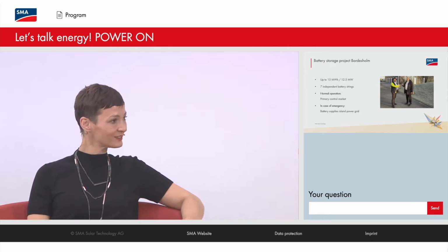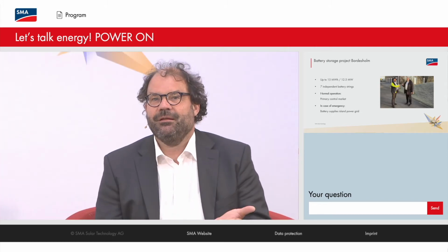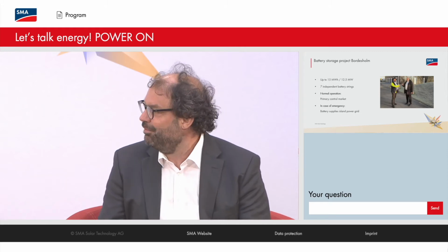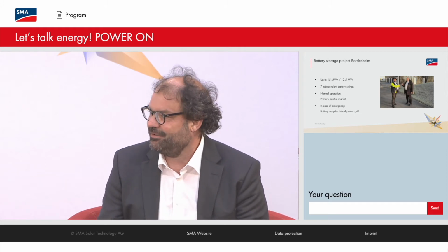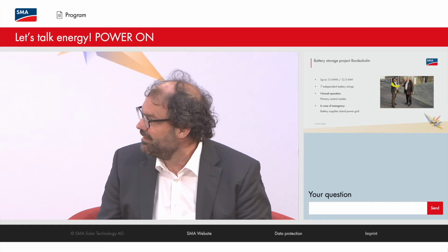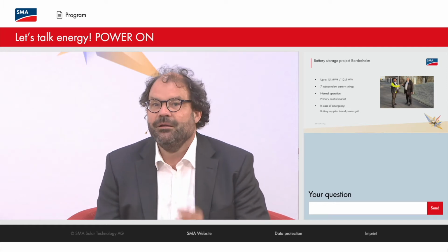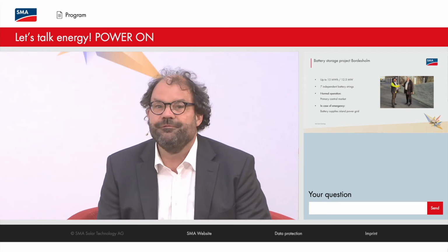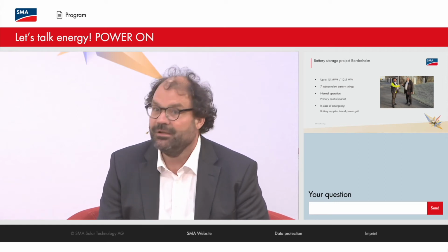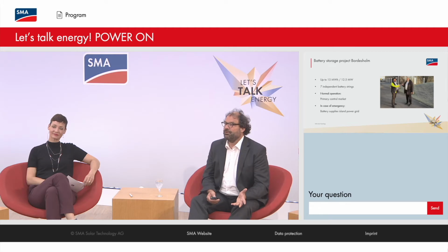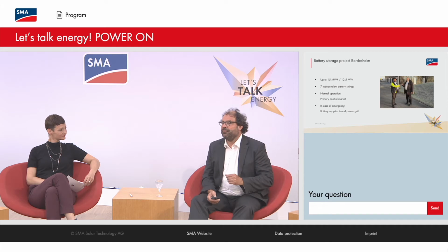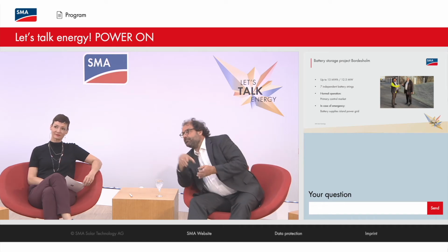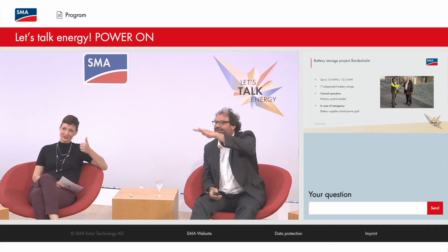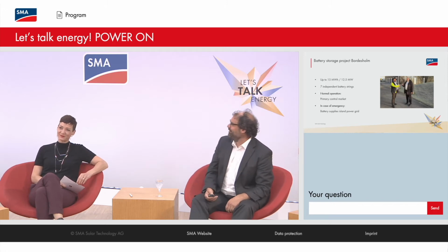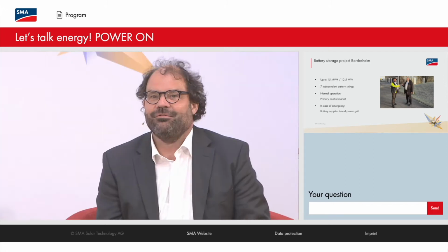What was the basis to realize this huge project? It's gigantic. The Versorgungsbetriebe realized that we have to do something for the future, so they invested the money to buy a battery of about 15 megawatt hours, with a maximum power of 12.5 megawatts, consisting of 7 independent battery strings. If you look at that picture, you can see 7 doors in the building, which correspond to the 7 strings of the battery.